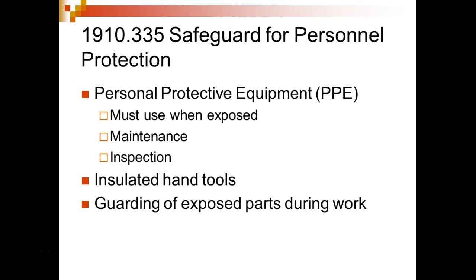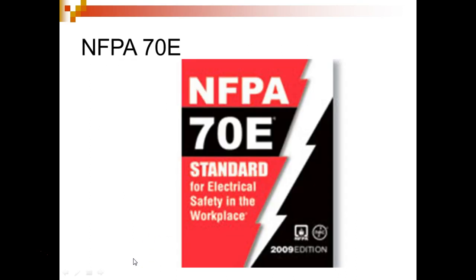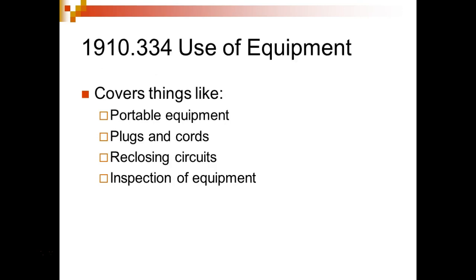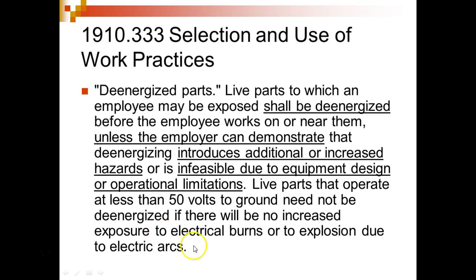Must use when exposed, maintenance and inspection, insulated tools. Insulated tools, too. So a lot of times you get into these high energy equipment, not only do you have to protect yourself, but you also got to protect your tools. Are we okay? This is 70E. It didn't tell us the exception. There is an exception in this standard, and that is if you troubleshoot. If you're a troubleshooter, we normally troubleshoot on live equipment. Everybody understand that? But if you're going to repair, if you're going to do maintenance on the equipment, then the equipment has to be what? Locked and tagged. Everybody has to be de-energized, locked and tagged. Everybody okay there?